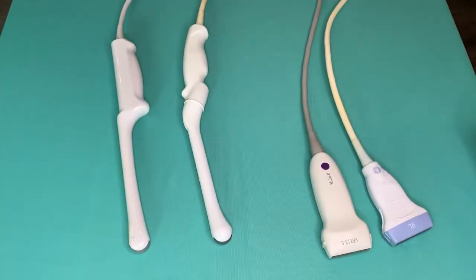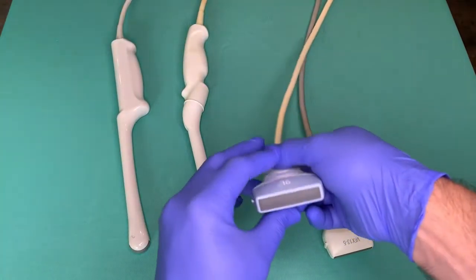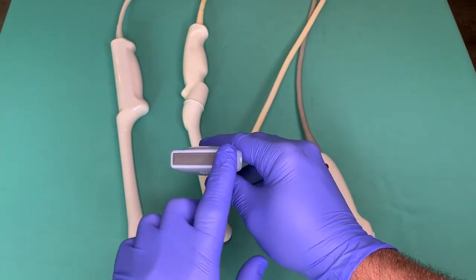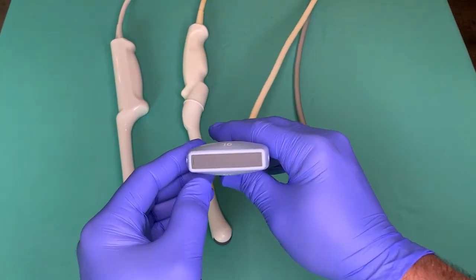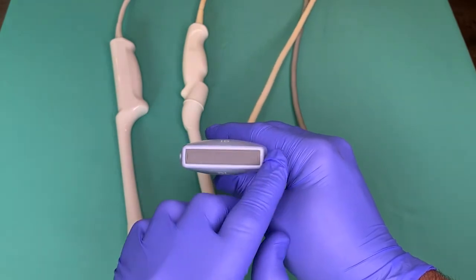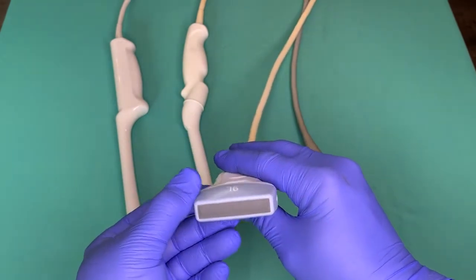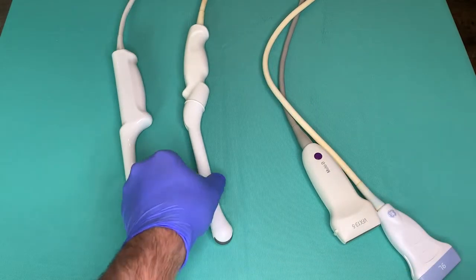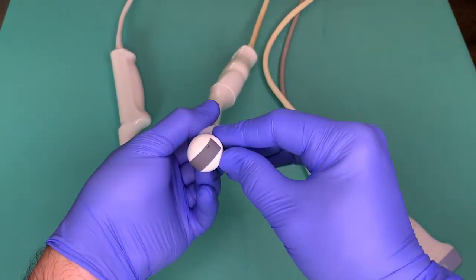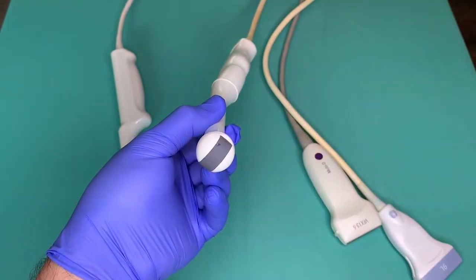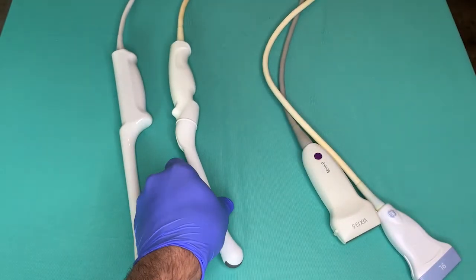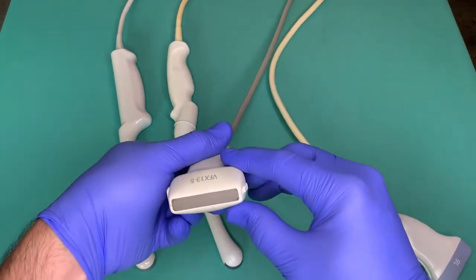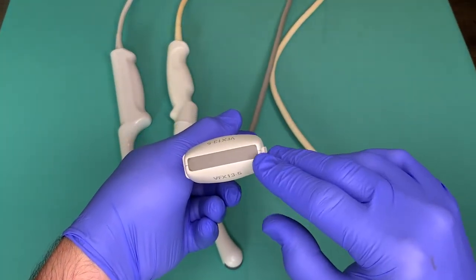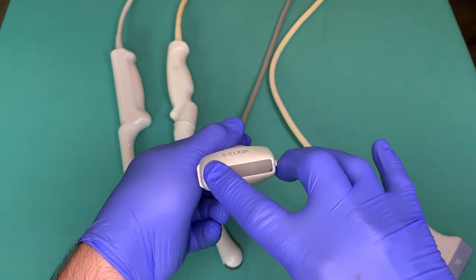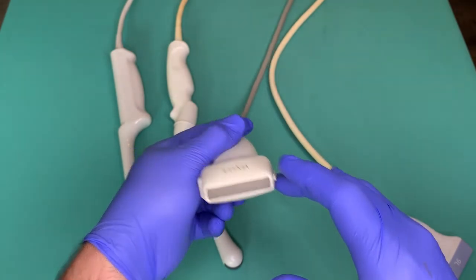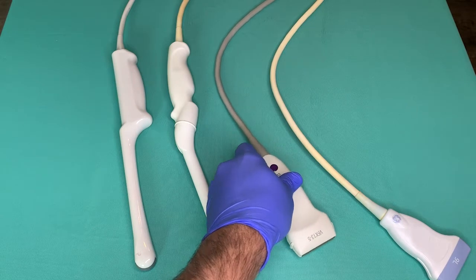The acoustic lens covers the acoustic array on a standard probe, which is a highly sensitive component. Typically, the lens is square or rectangular in shape and has a rubber-like appearance. The lens on most probes is surrounded by a gray or white sealant. Inspect the lens under magnification, looking for cuts, holes, deep gouges, and areas where the lens material may have worn away. Inspect the seal surrounding the lens under magnification for any inconsistencies or lack of fill. Any area that is believed would allow fluid entry should be addressed with a high priority.